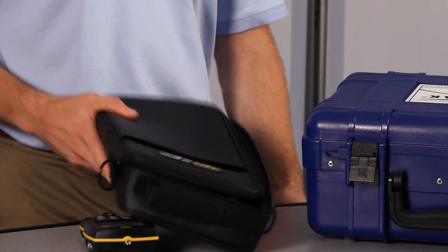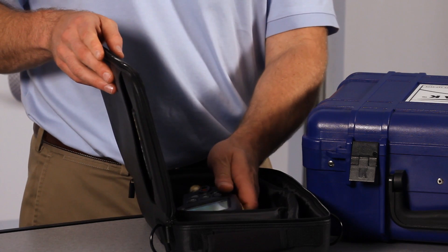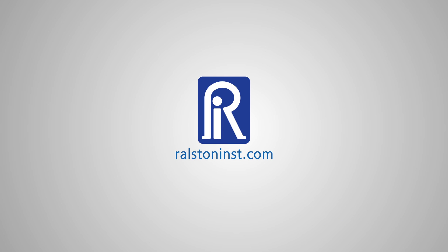This also makes it very easy to store your pressure calibrator separately from your control device or hand pump. NPT male quick test pressure calibrator adapters are available in a range of NPT sizes. Adapters come in brass or stainless steel — if you have a chemical compatibility issue such as sour gas, select stainless steel. For pressures above 5000 psi, use our quick test XT models. Check out our website for detailed specifications and other time-saving pressure calibration products.